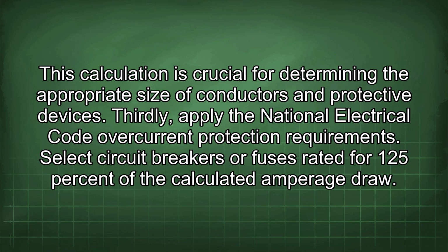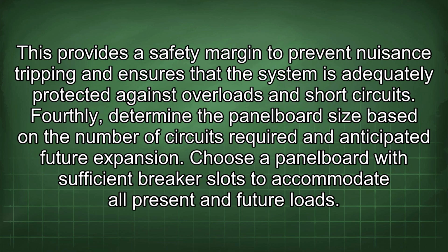Thirdly, apply the National Electrical Code overcurrent protection requirements. Select circuit breakers or fuses rated for 125% of the calculated amperage draw. This provides a safety margin to prevent nuisance tripping and ensures that the system is adequately protected against overloads and short circuits. Fourthly, determine the panel board size based on the number of circuits required and anticipated future expansion. Choose a panel board with sufficient breaker slots to accommodate all present and future loads.